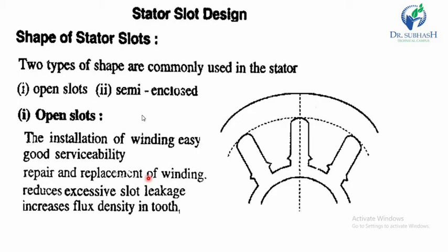This type of slot has greater flexibility to assemble any winding, so the repairing of the winding is easy. However, such a slot will lead to a higher air gap contraction factor, which means that the flux distribution is affected and the magnetizing current is higher, and there is a poor power factor.